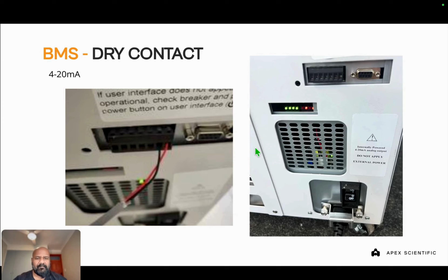However, this just gives you the alarm signal - it does not tell you why the freezer alarmed. Remember, we have many different types of alarms, including door alarm, condenser high temperature, cabinet high temperature alarm, freezer malfunction. So the freezer alarms and you don't really know why. Sometimes when researchers or lab technicians open the freezer door for over a period of time, I think it's 5 minutes, the alarm starts buzzing. So all the alarms are the same and you wouldn't know how to respond, but this feature is here. It used to be very popular in the past, not so much these days.